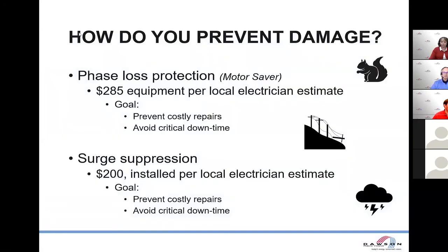Not a real costly investment. As you see, we've talked to some local electricians, and roughly $200 to $300 will put this piece of protection in. A lot cheaper than replacing a multi-$1,000 motor or control panel. Another type of failure that we see out in rural America, of course, is transients. To protect from those types of incidents is a surge suppressor. This is typically installed right at the motor, to protect from lightning damage, and to protect from some other failure within the actual irrigation system itself. Another fairly reasonably priced insurance policy, if you will.